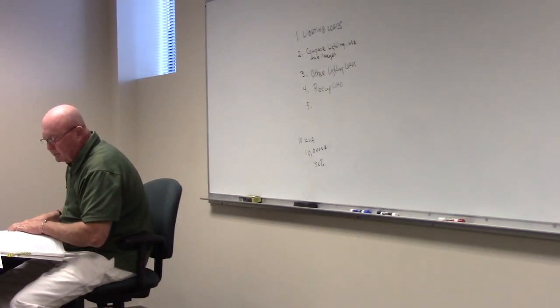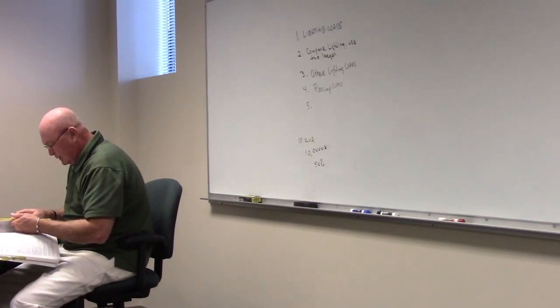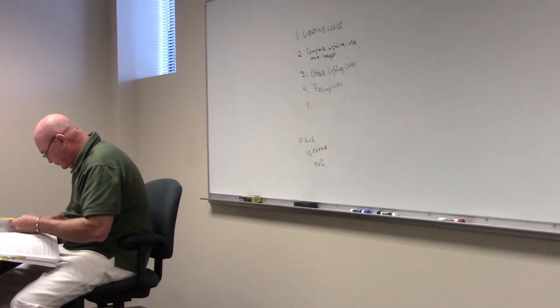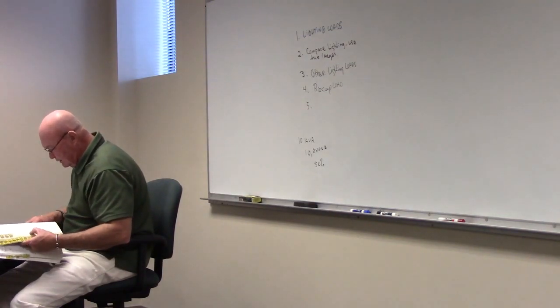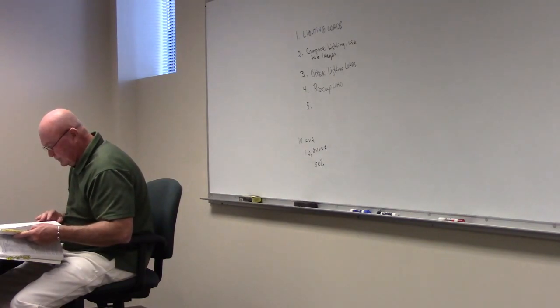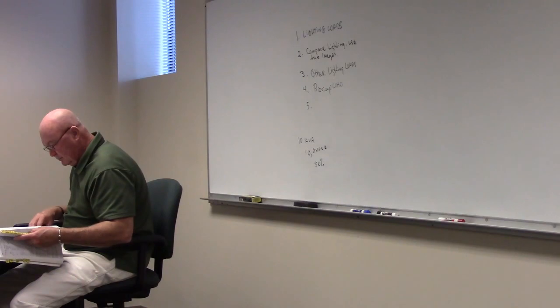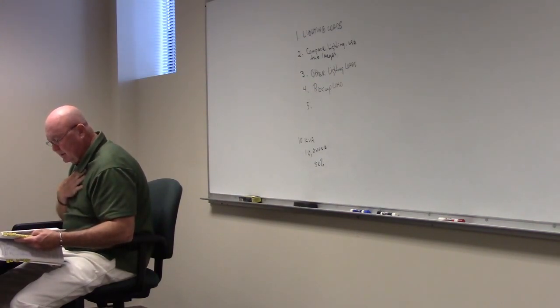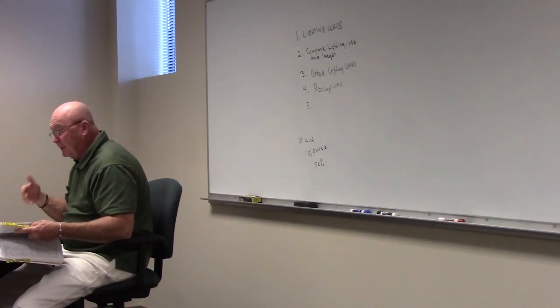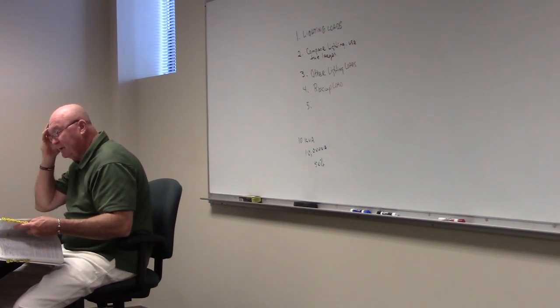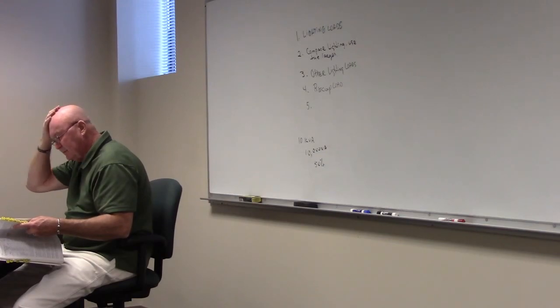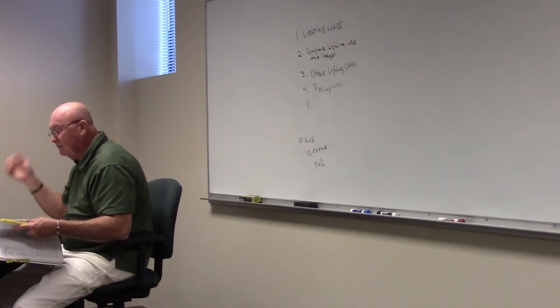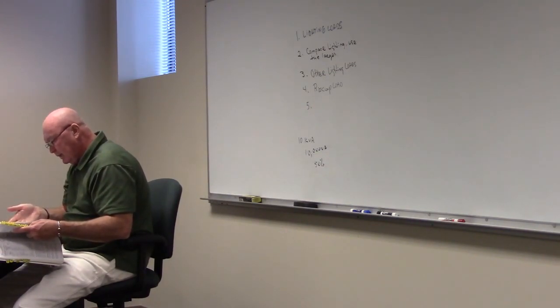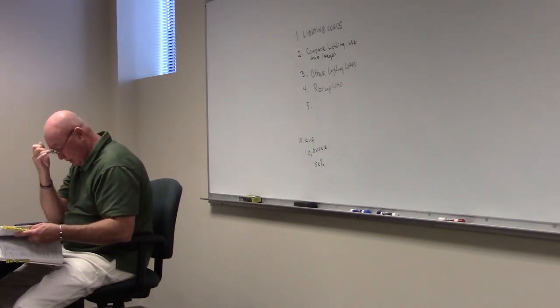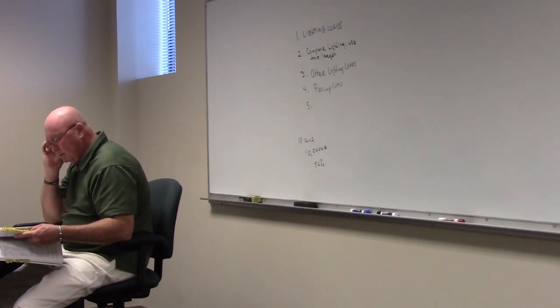Let's look at these other articles right quick. Article 610 talks about, this would be a commercial installation here. 610 is cranes and hoists. And there's a demand factor, 610.14(E), number of cranes or hoists. And again, James, you did a crane installation over at, what's the name of that place? All Metals. Oh yeah. Do they typically run all the cranes at one time? No. One at a time. And so because of that, there are factors here. Like 5 cranes, the demand factor is like 0.84. Y'all see that table there? Which table again? 610.14(E).